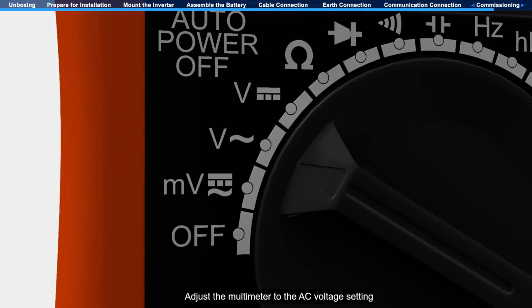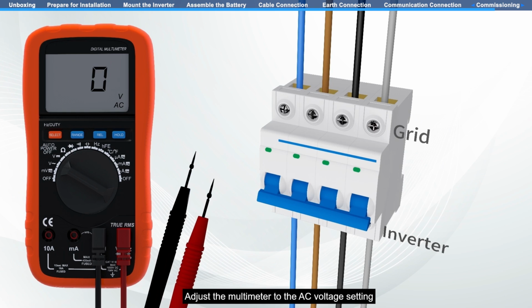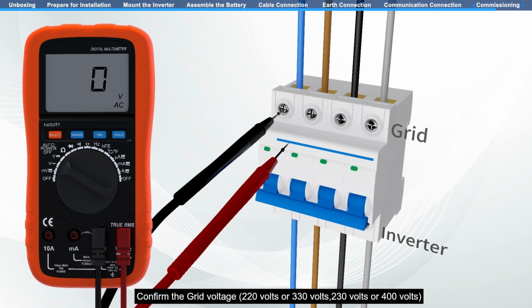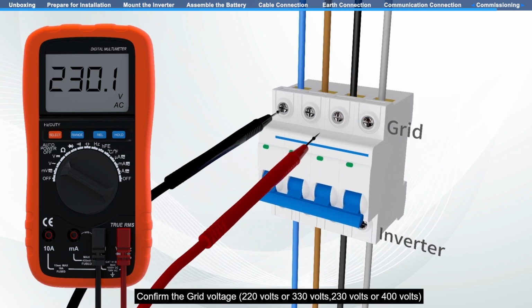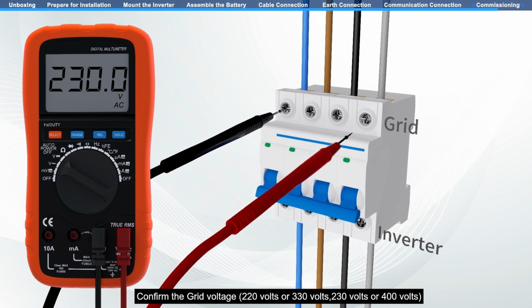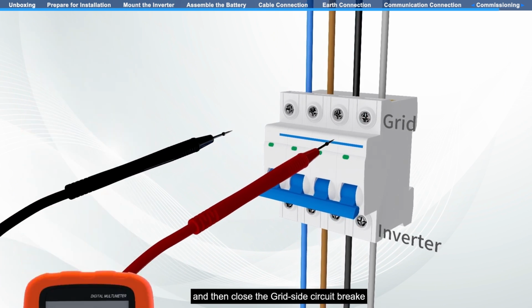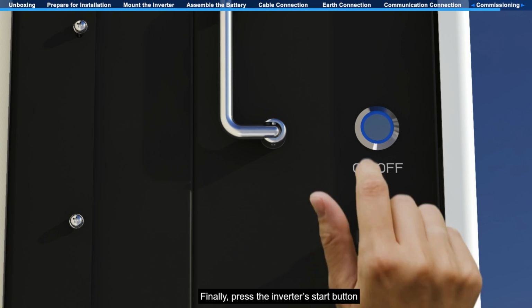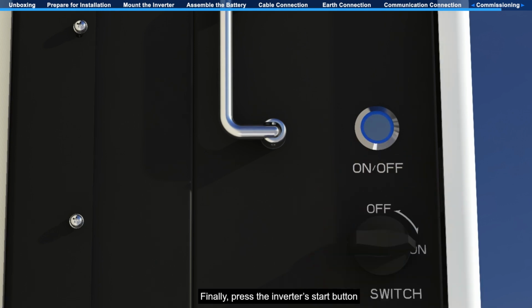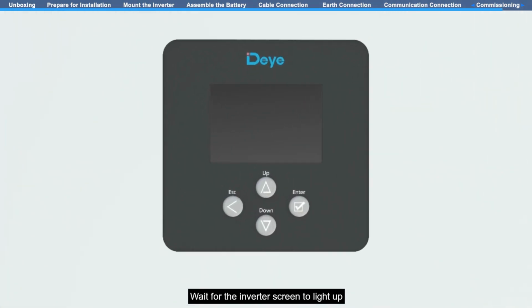Adjust the multimeter to the AC voltage setting. Confirm the grid voltage, 220 volts or 330 volts, 230 volts or 400 volts, and then close the grid side circuit breaker. Finally, press the inverter's start button. Wait for the inverter screen to light up.